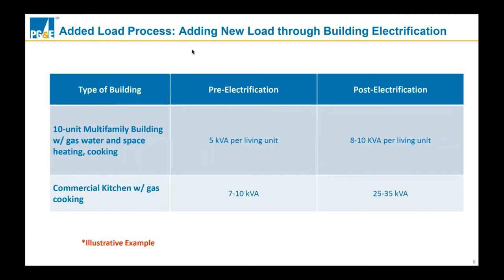Pre-electrification, you might see a demand of 5 kVA or so per living unit. Post-electrification—electrifying the space and water heating, electrifying the cooking—on the high end, you might double that and see 10 kVA per living unit. Hopefully you're adopting some of the things John and Barry talked about in terms of lower amperage appliances and such, but if not, this is the type of incremental load you might see in this particular illustrative case.